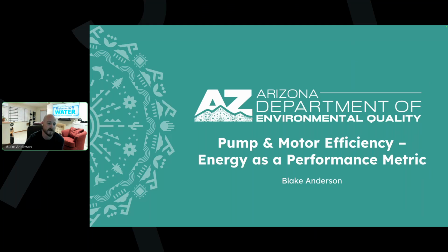of costs and actually cut down on a lot of breaks. I'm pretty proud to say that some of our systems, just by making some small control adjustments and pressure set points, we've been able to drop the number of breaks by 50% compared to what they had been doing previously. Unfortunately, that's just oral tradition coming from the people who were on the board that had been there previously, because they didn't have the data being collected to actually be able to say that. But that's what they report, and so it definitely can be done.